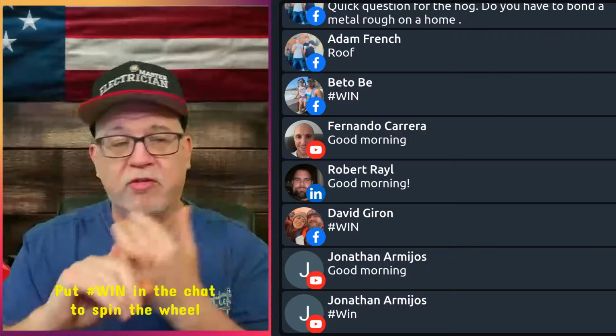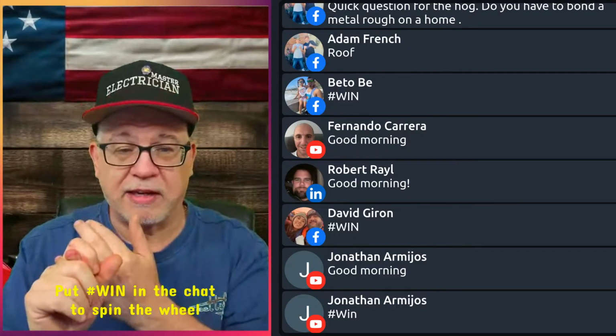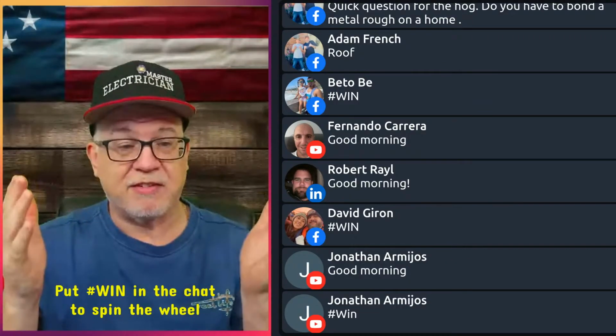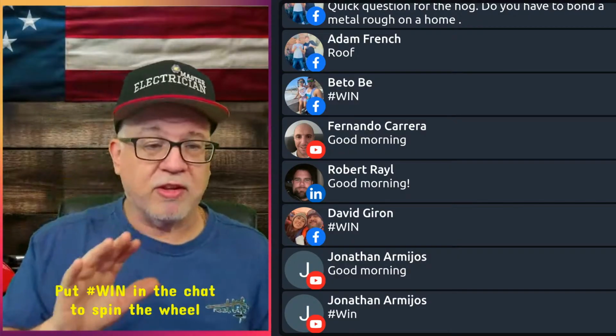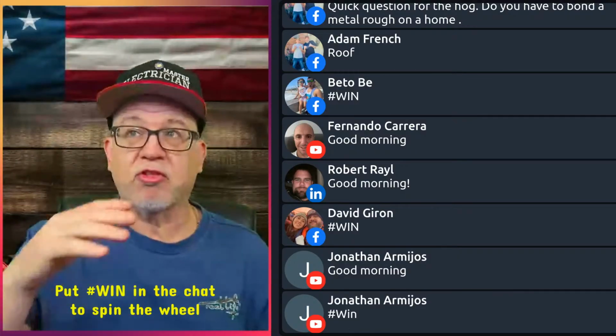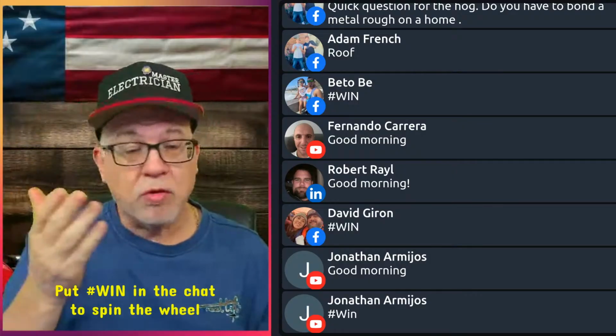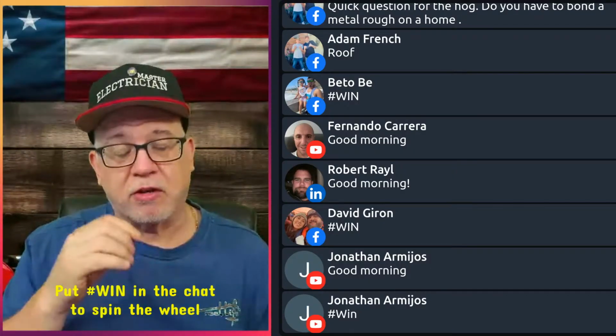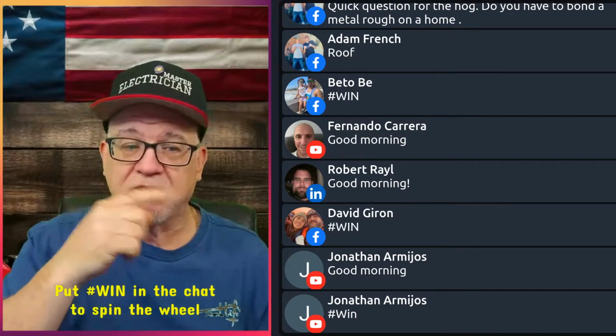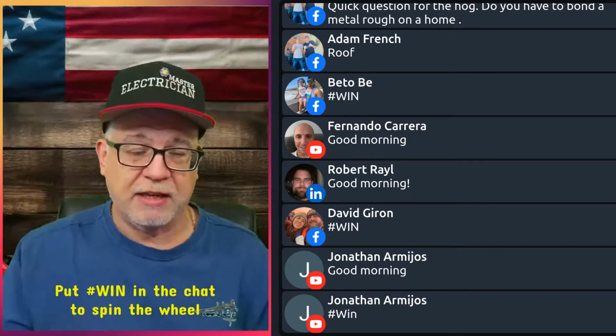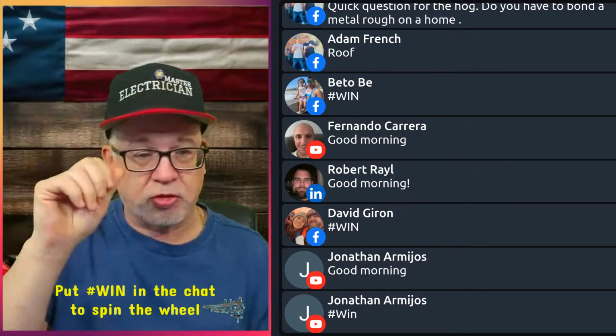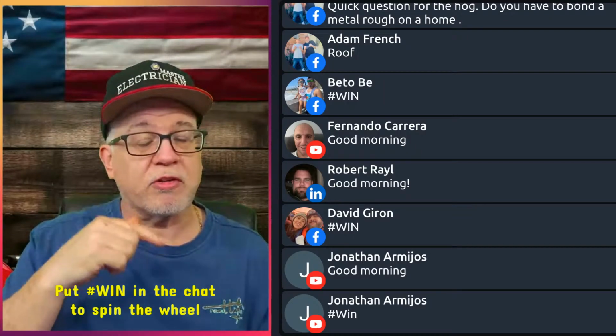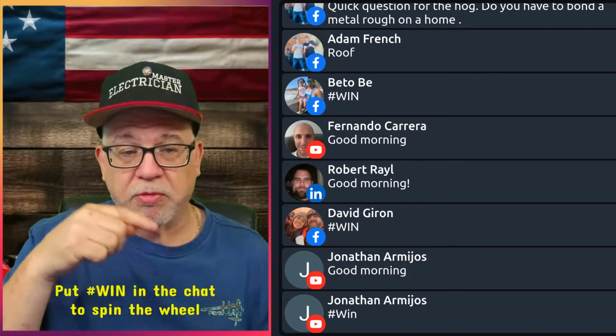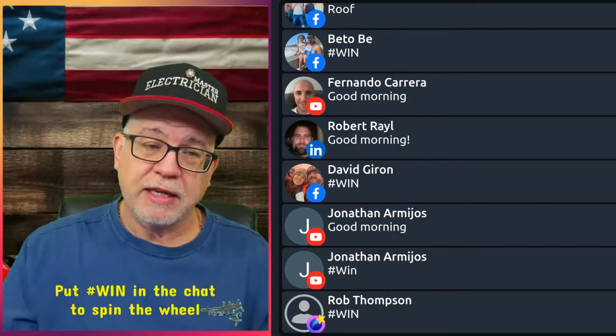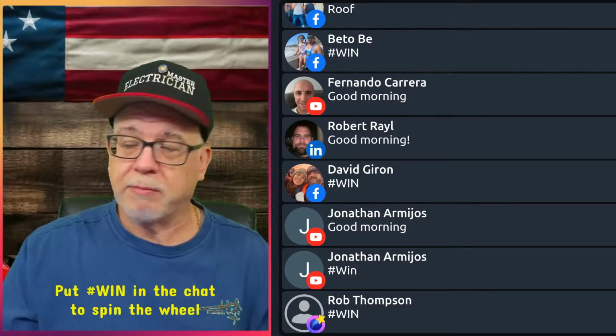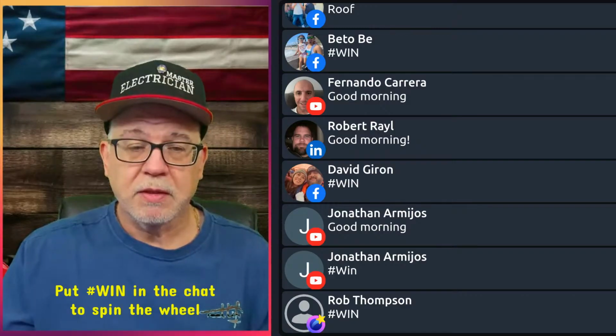So it's both. It's the emergency disconnect labeled as such. It's the service disconnect labeled as such. Okay, NEMA 3R, it's exterior. That panel has all the loads in it. Okay, every breaker that's associated with this dwelling. Then you can apply the 83% rule. And that means the service conductors never need to be larger than 83, but they can't be smaller than 83% of whatever the service rating is. And that's based on whatever the breaker is. If the breaker is a 200 amp, then the service conductors cannot be less than 83% of that service rating. Can they be greater? Yeah. Can you size it to the full 200 amps if you want? It's not a problem. Okay.